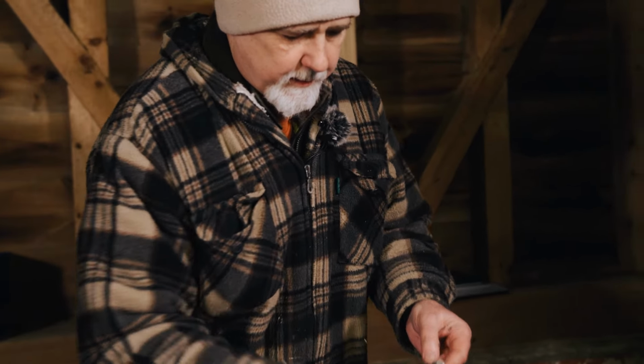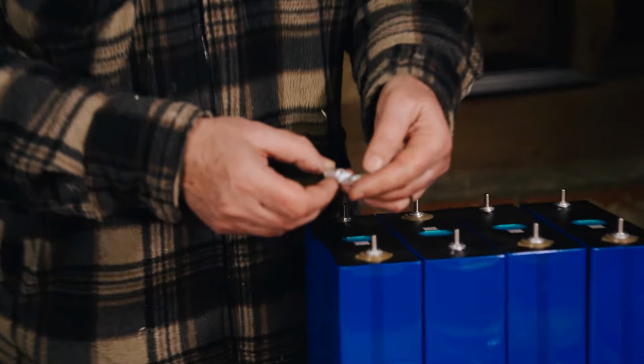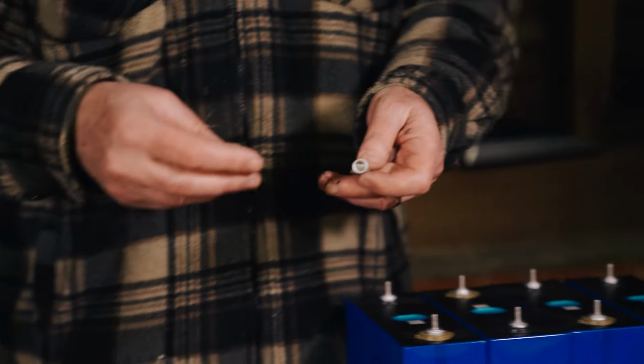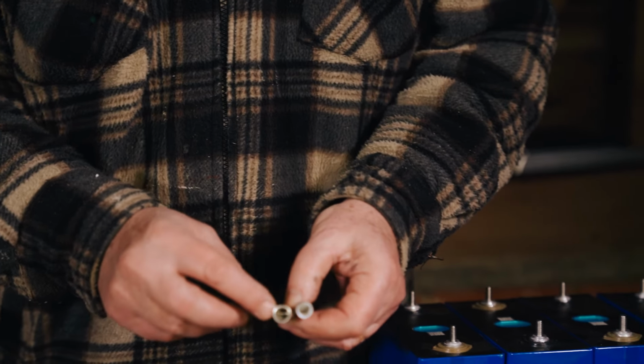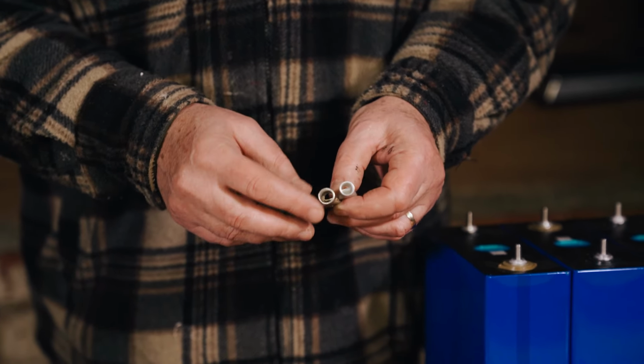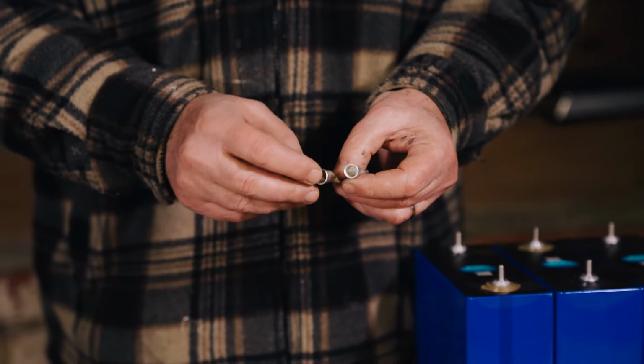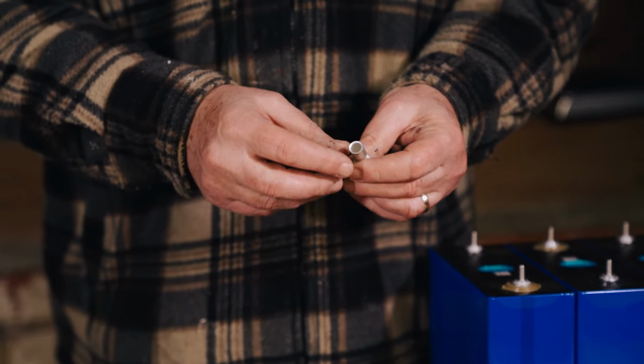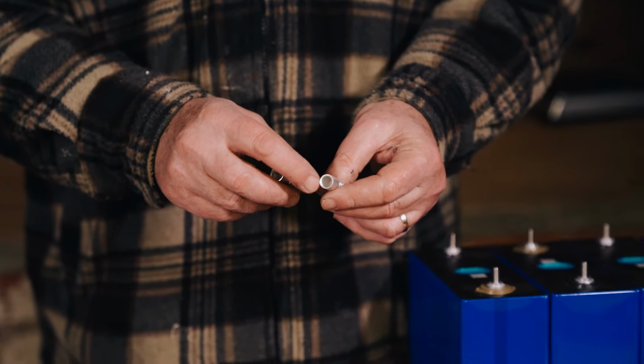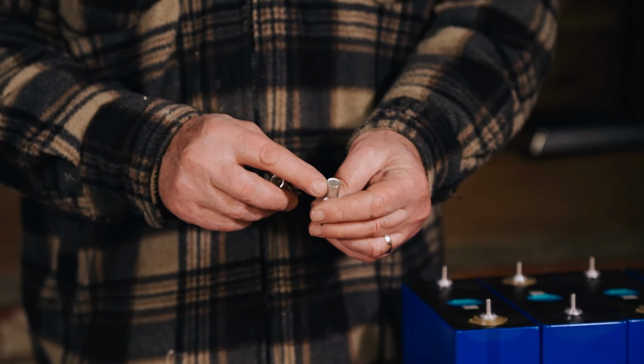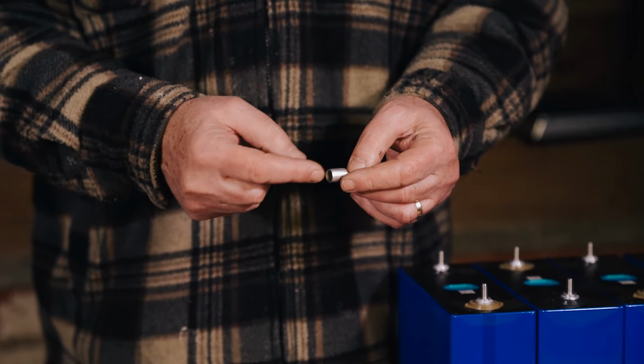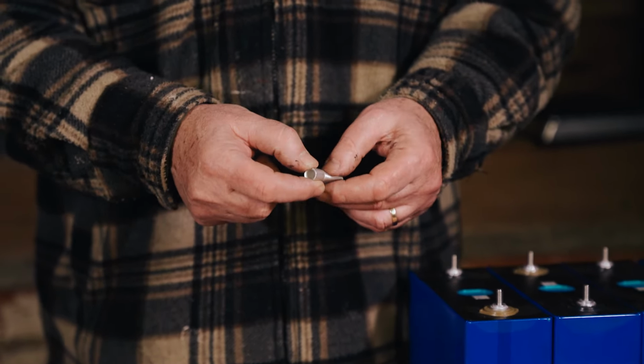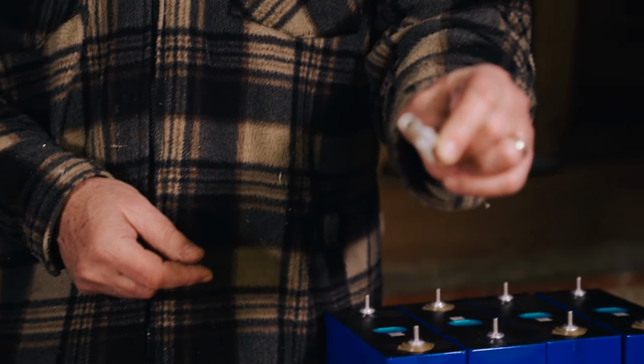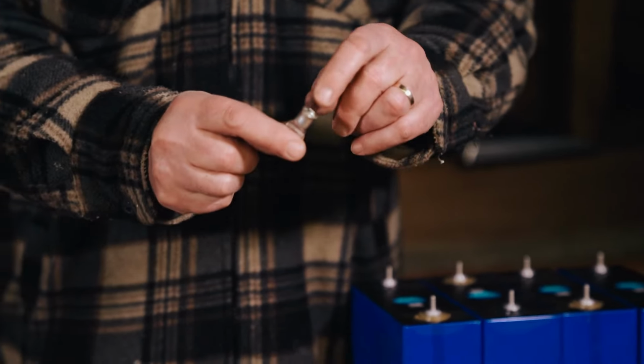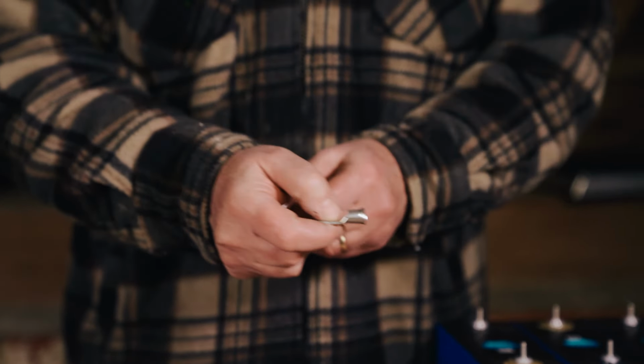I just want to show you two different types of lugs. These are 35 by 8, and this is also 35 by 8. You can see this one, the edge is flanged out a little bit, which makes it a lot easier to insert the cable you're going to crimp. This one, where it's not flared out at all, makes it quite difficult to get the cable in without a few strands coming out and going loose. So I would recommend don't go for these if you can - rather go for these where it's flared out and really easy to get the cable in.